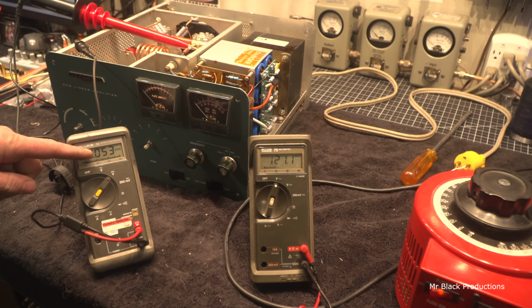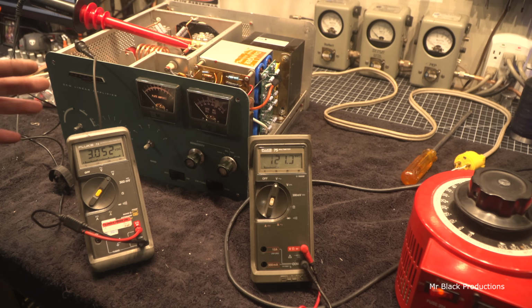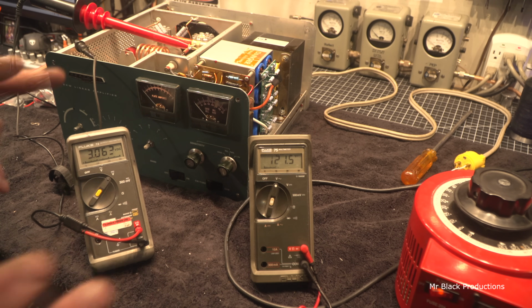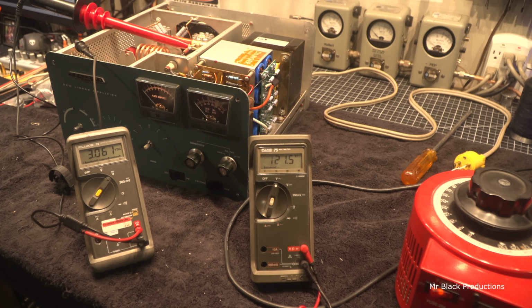See this margin here? Not error, the margin in the capacitor - we're giving ourselves 500 volts worth of capacitance margin in the capacitor bank. There's a 500 volt window. There's 3,500 volts worth of capacitor here, so we can run up to 3,500 volts, but that's its maximum.